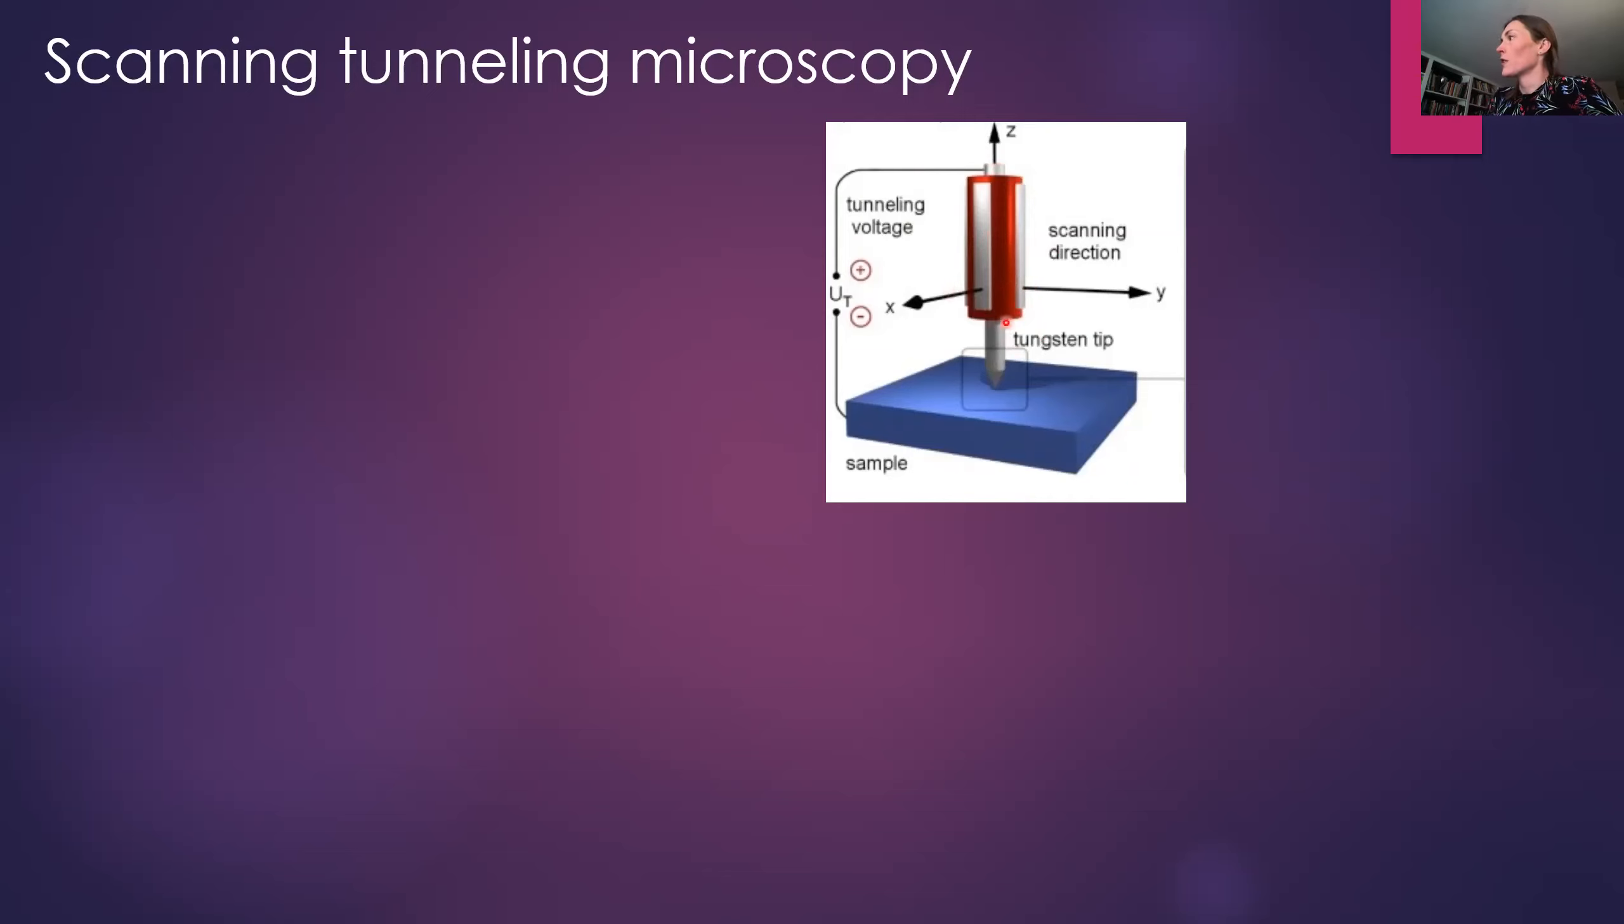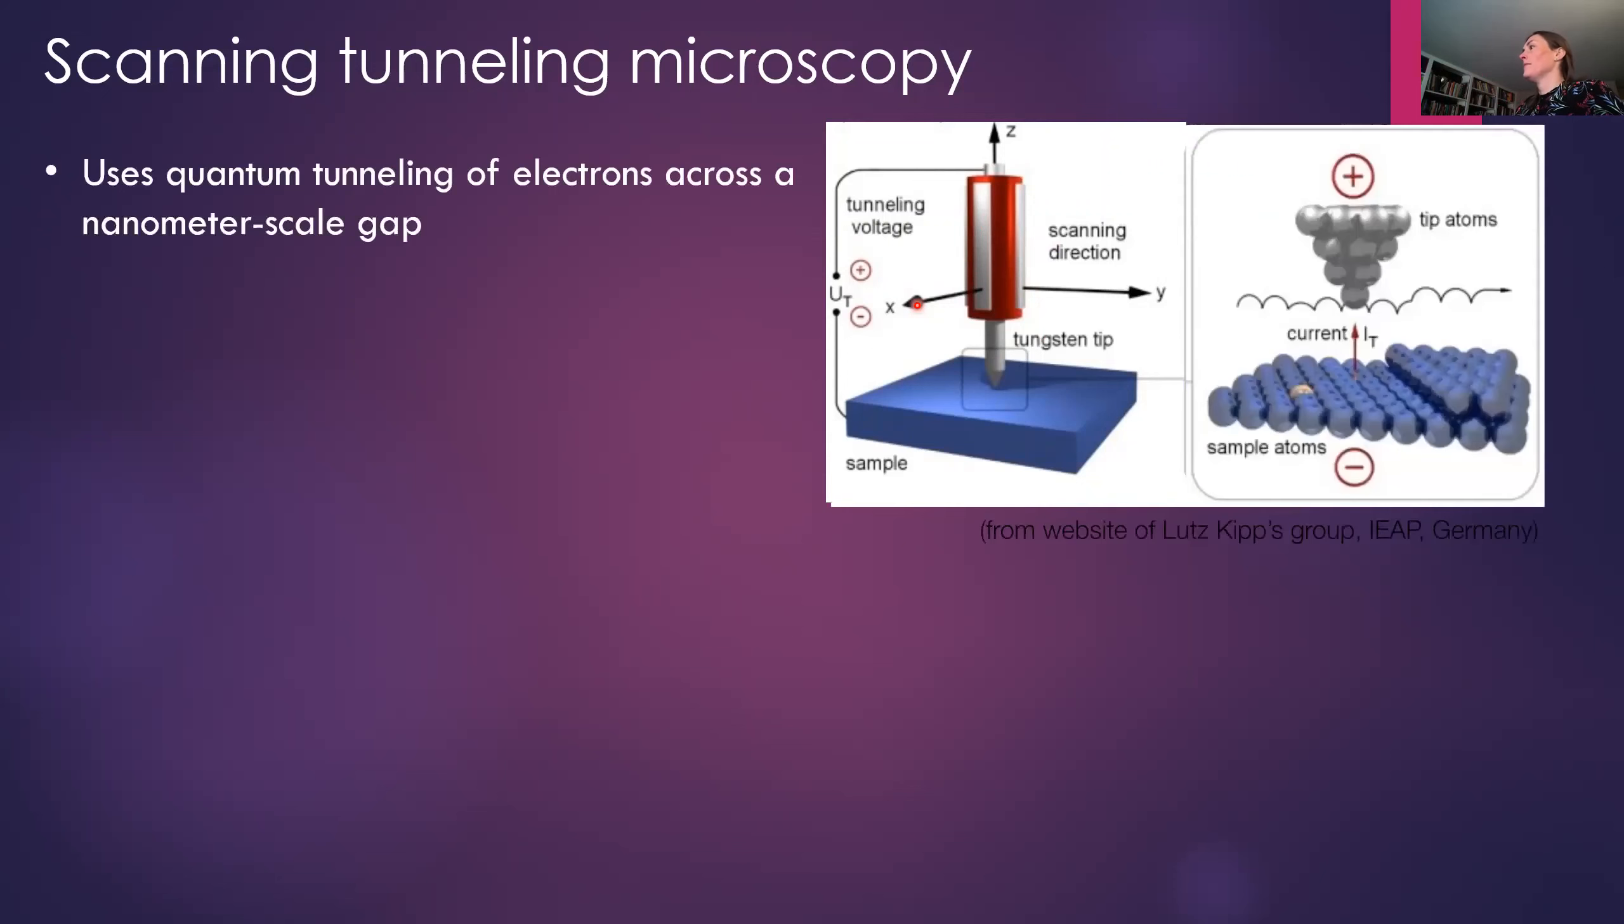So you control the distance between the tip and the sample with this high voltage on these piezos. And then you can also use the same principle to control the motion of the tip across the surface. That's how you get an image. You don't only want to just tunnel in one place, you want to tunnel in that place and compare it to the next place. On the atomic scale, you have the tip atoms and you have the sample atoms. And this gap here is on the order of one nanometer in order for there to be some reasonable probability that an electron will tunnel from one material into the other. And in order to get that tunneling to occur preferentially in one direction, you apply a voltage between the tip and the sample.